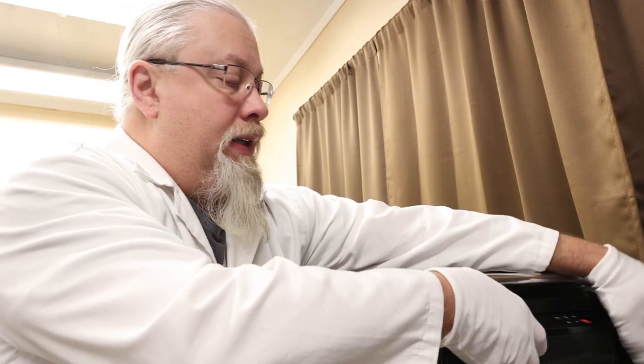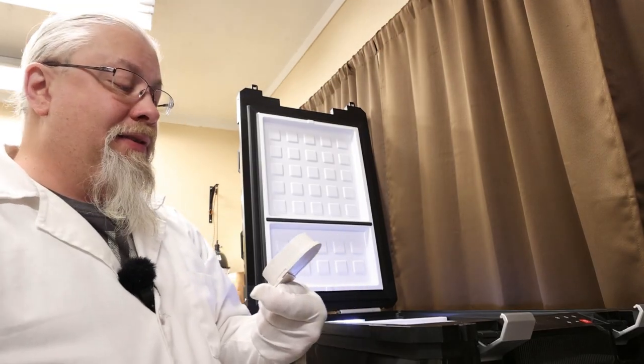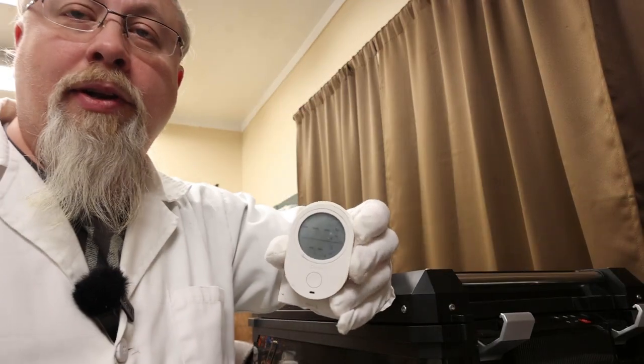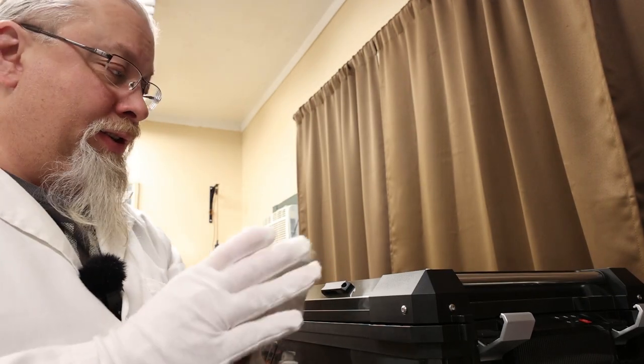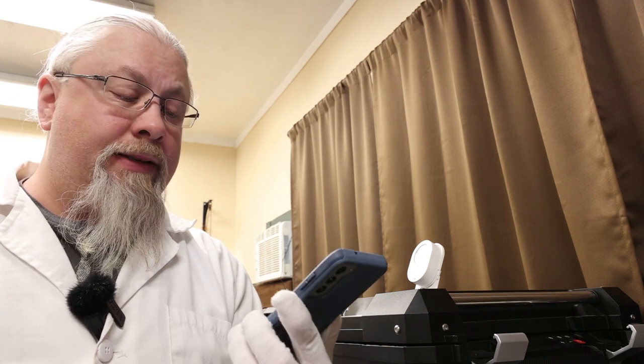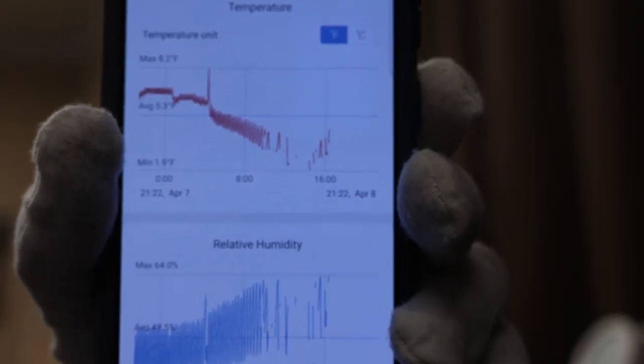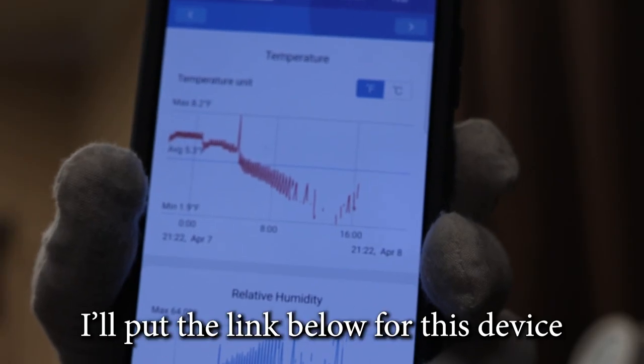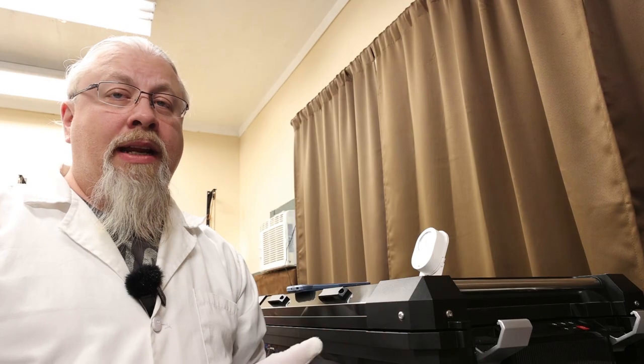Now let's see what the thermometer inside says. Remember we left that in there on the freezer side and it's not reading anything. Looks like it got so cold—oh wow it says minus 15—apparently got so cold it wrecked the battery inside. I might have to let this warm up, but then that's gonna throw off the temperature. Still not telling me anything. Now I can probably Bluetooth to this and get the history if it recorded the history. So let's see if I can do that. So it looked like the cold kind of killed the battery and it didn't save all the data, but it did go down to 1.9 degrees. You can see over here on the left hand side it says minimum 1.9 F. So that was where it was sitting at last night, 1.9 degrees. And seeing that I had it set at zero, that's pretty good.